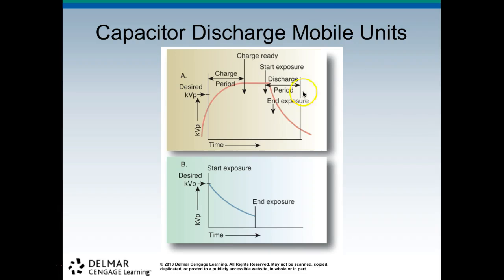So you can see here we ramp up the kVp, and this is our charging period. Once it hits the charge, a signal comes on, you can start the exposure, and then it drops here, but it's still inconsistent. So you have to be careful with these units.